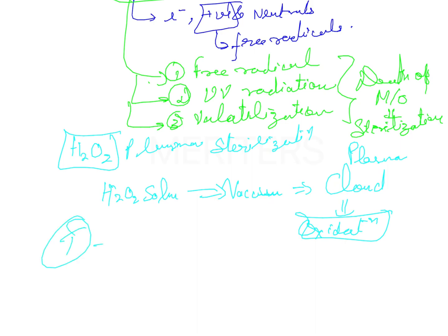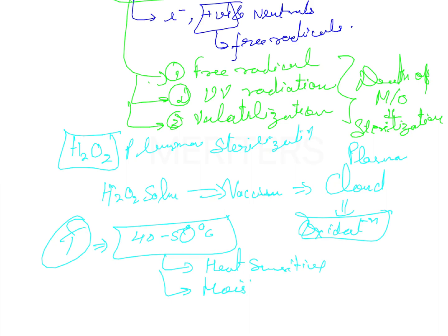What is the temperature range of plasma sterilization? It is between 40 to 50 degrees Celsius. It is particularly well suited for use with heat-sensitive as well as moisture-sensitive medical devices. Since the temperature is only 40 to 50 degrees Celsius, you can safely use heat-sensitive and moisture-sensitive instruments in this process.